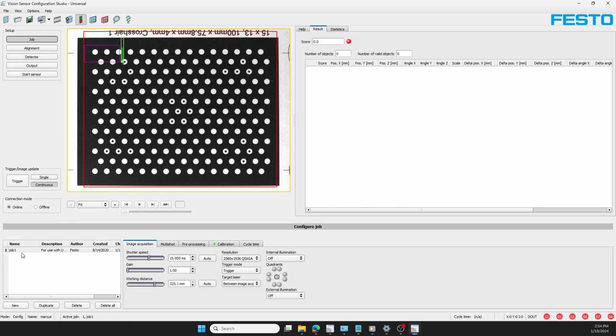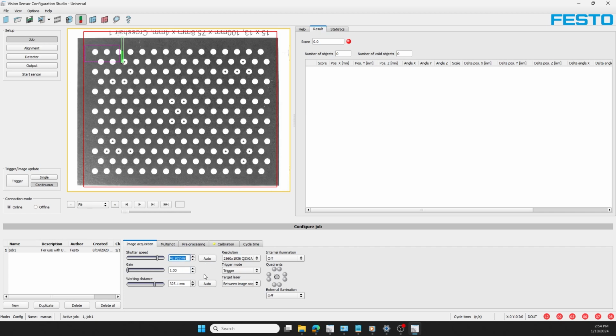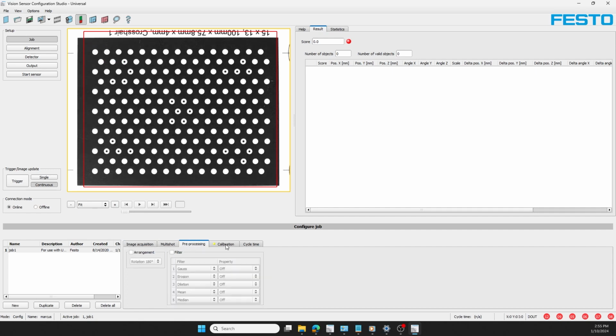You can see here that we have a clean view of the 100mm calibration grid using lowercase job1. We'll auto set the working distance and shutter speed. Once the working distance has been set, it cannot be changed for the rest of the calibration. The shutter speed can change to create the greatest contrast required. I also have the trigger mode set to trigger. My internal illumination is turned off.